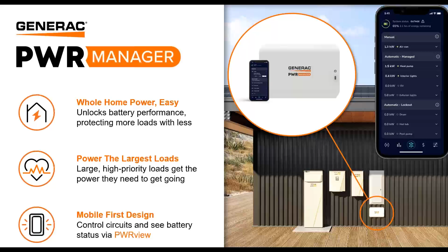The problem with really all backup systems is that if you don't have load management—and this is true for generators as well—and a system is overwhelmed with consumption in the house, the whole house loses power, assuming you're doing a whole house install. That's going to drive a call to you, the installer, from a disappointed homeowner whose system didn't back up the house in an outage. It's probably one of the worst calls you can get.